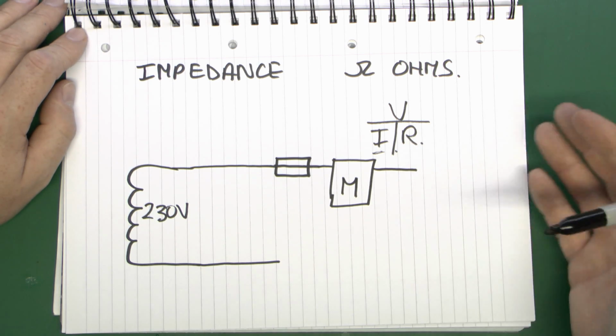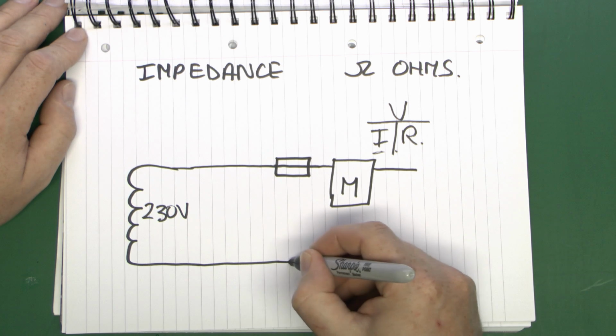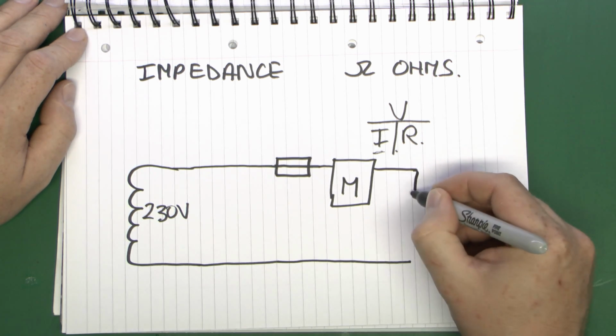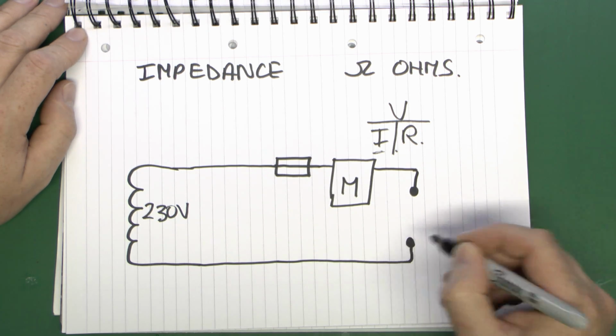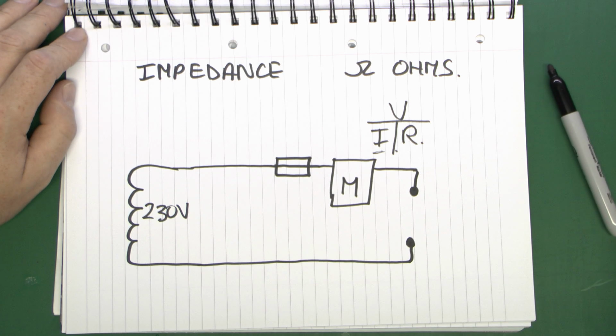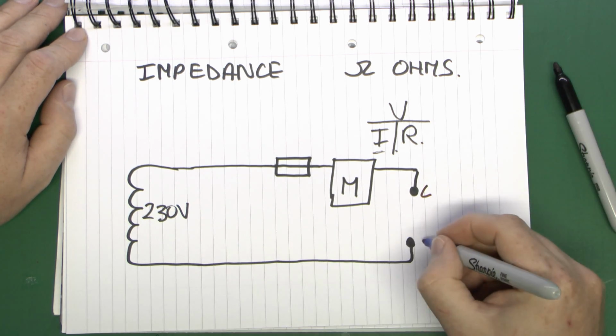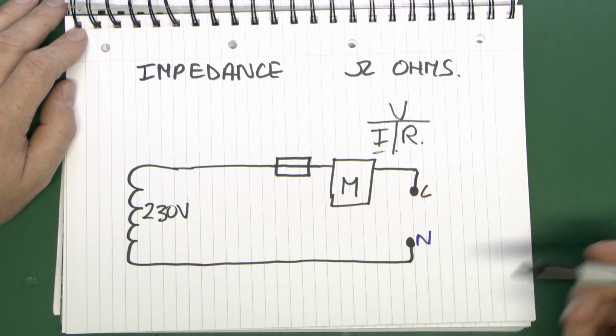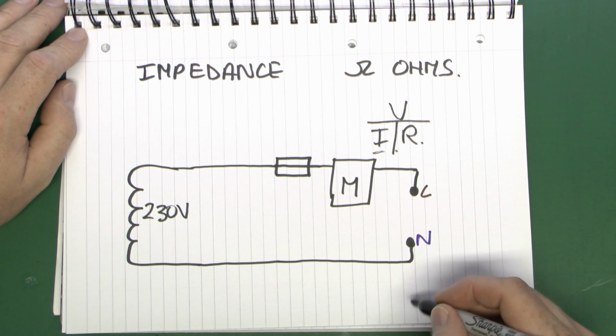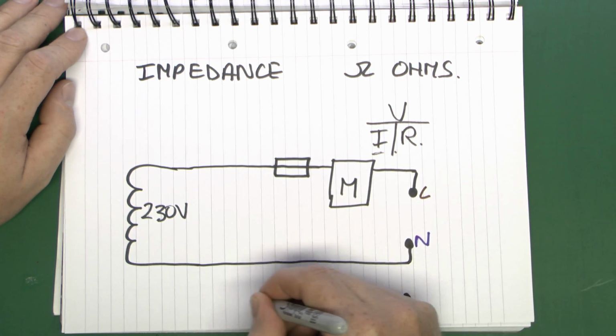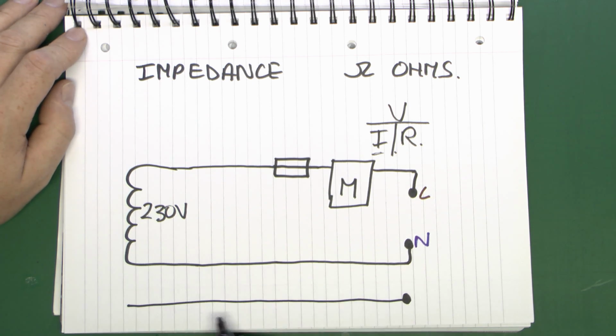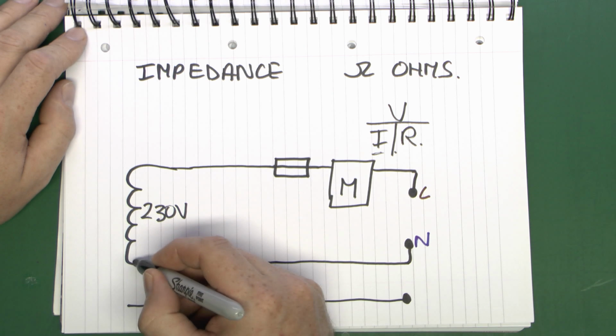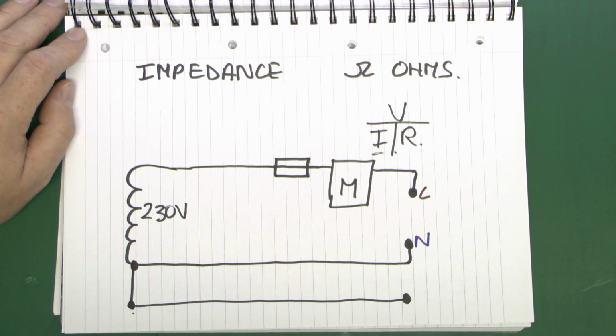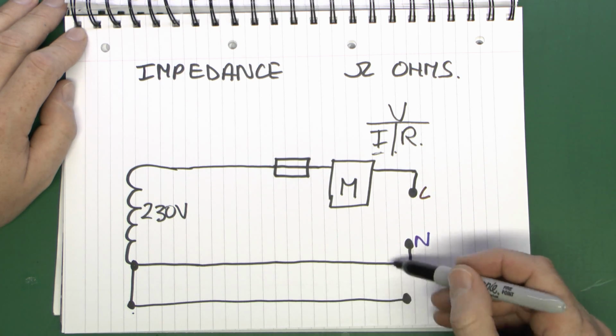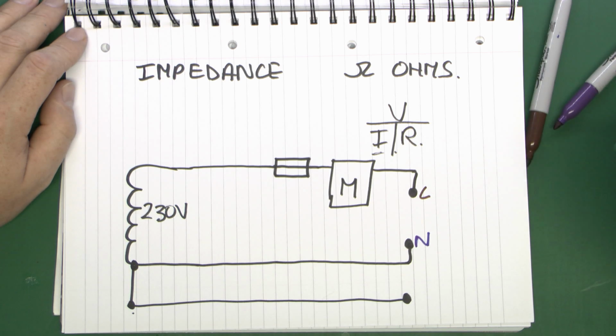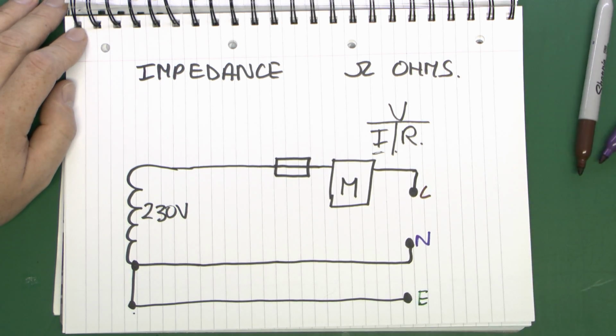And then you're going to have your consumer unit with fuses and devices and circuits extending on into the building. But if we can just consider for the moment the terminals we've got here. And these, of course, can be just marked up here as line and neutral. Now, of course, there's also going to be an earth connection as well, so we'll just draw that in at the bottom here. Let's draw it as a TN-S supply, so you've got a separate earth conductor going back to the transformer, and the transformer is always going to be connected to the neutral in there. Of course, it might be connected here if it was the TN-C-S type of supply, but in any event, there's certainly going to be an earth connection coming in.